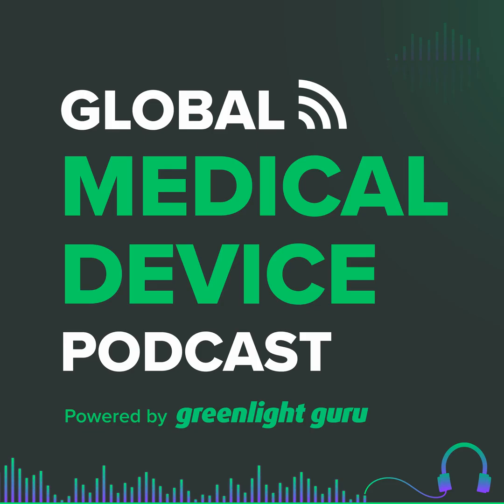Yeah, good question. And just as a reminder to you and our audience, I work as a consultant for the FDA, so I see these issues on both sides. Just giving approval based on a protocol without having data, I think is going to be difficult for most FDA reviewers to swallow. Now, here's my potential fix for that, because I like to pride myself in coming up with solutions, not making excuses. So, what I would advise my customer, and this is exactly what I've been doing in the last year or so since we've been using these PCCPs, is include your protocol.